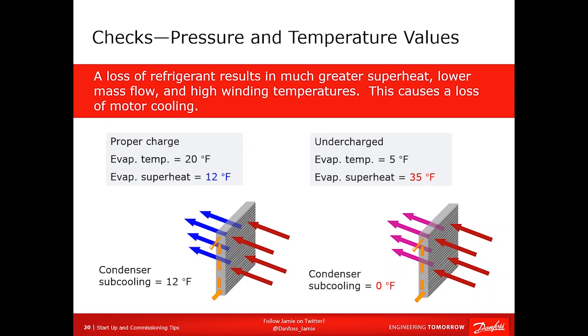What you need to do is figure out where your subcooling is going. What is plugged downstream? So verify evaporator temperature, superheat, and the fact that you have no condenser subcooling before you add charge. And even then, before you add charge, you got to ask yourself, where'd the refrigerant go? All right? Did somebody undercharge it? Well, considering that almost 2/3 of all systems are overcharged, I highly doubt it. It could happen. More likely, there's a leak somewhere, and you've got to figure out where it is before you start dumping refrigerant in there.